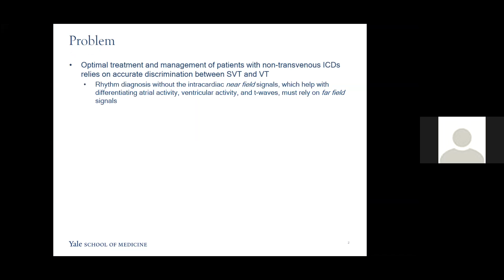In traditional transvenous defibrillators, these devices can use intracardiac near field signals, which allow for much easier differentiation of atrial activity, ventricular activity, and T waves. However, non-transvenous devices must rely exclusively on far field signals, which are much more difficult to analyze, and misidentification of an arrhythmia can lead to morbidity, mortality, or impaired quality of life due to either undertreatment or overtreatment. The Achilles heel of Boston Scientific subcutaneous ICD is the inappropriate shock rate for T-wave oversensing and oversensing of myopotentials.